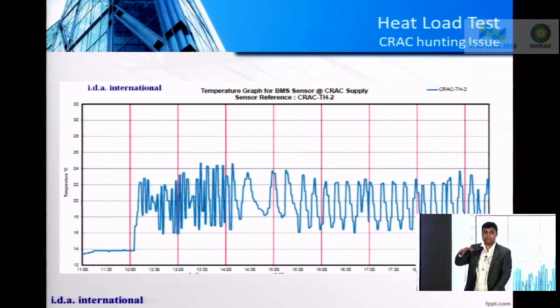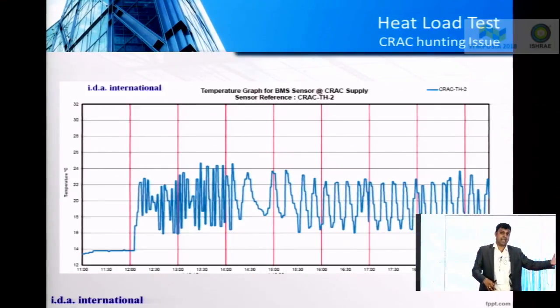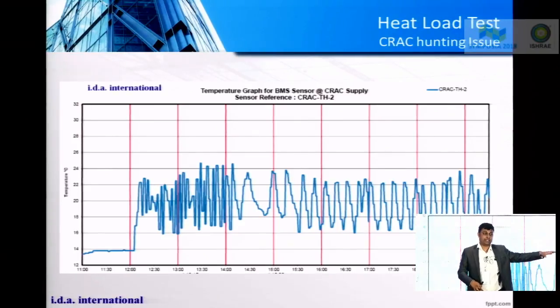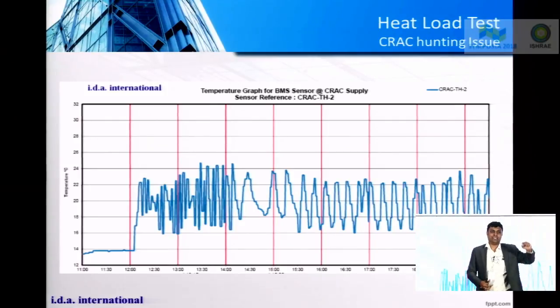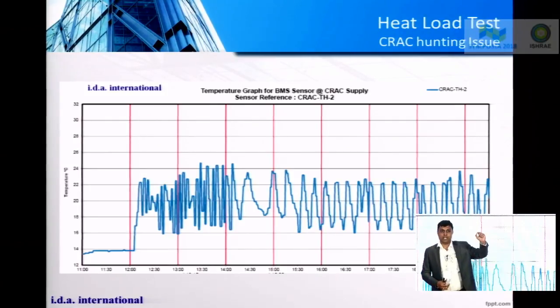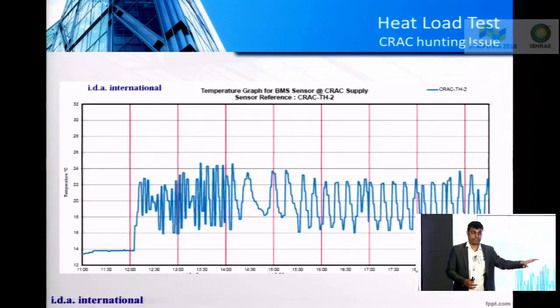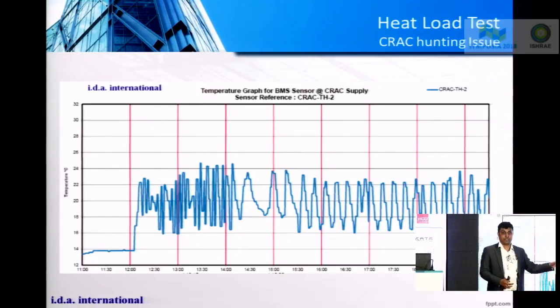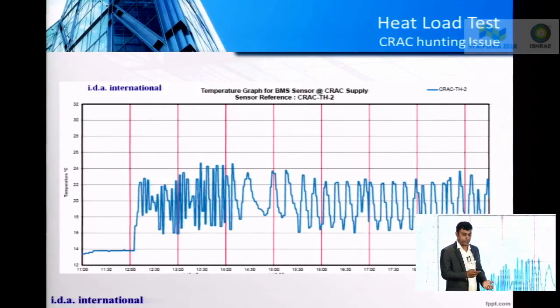So if I'm getting plus or minus 6 to 8 degrees Celsius fluctuations at the CRAC level, I could get 3 to 4 degrees Celsius fluctuations at the cold aisle containment, which is not good because there are likely chances that you're crossing the SLA limit frequently. So these issues have to be avoided. We call this the CRAC hunting issue. It's one of the issues that you can identify during the heat load test.